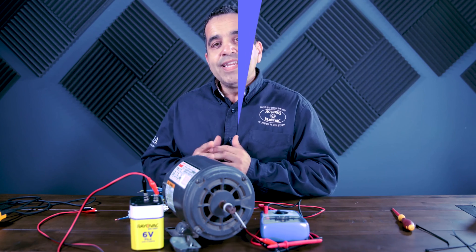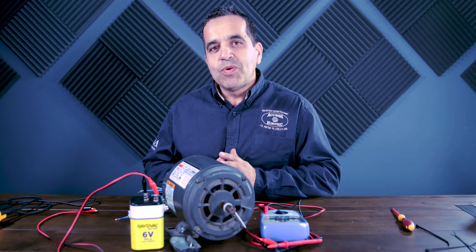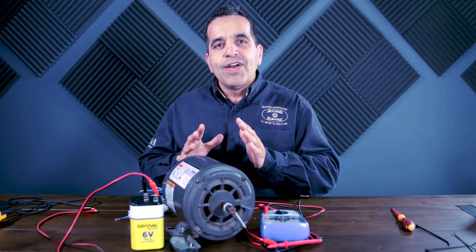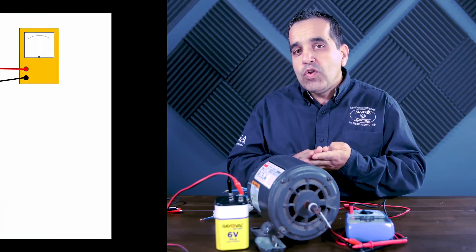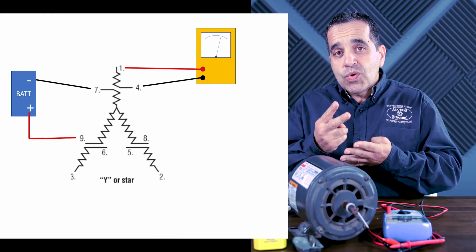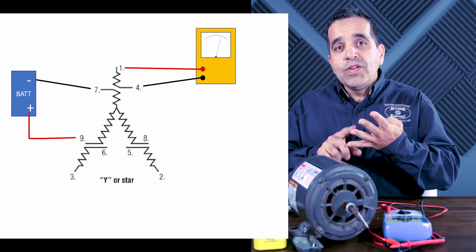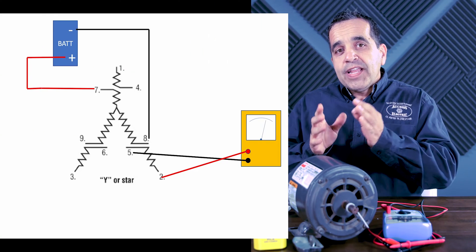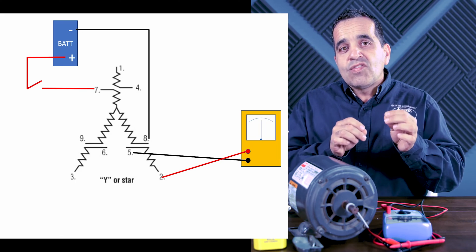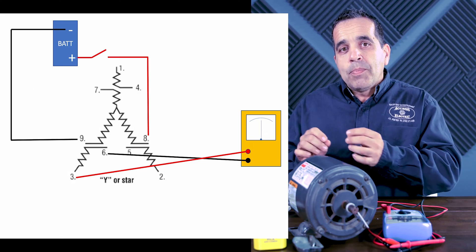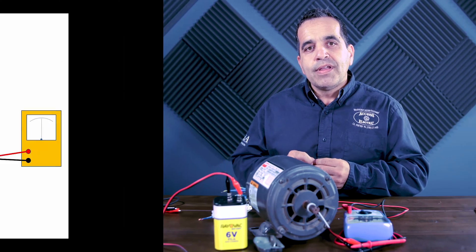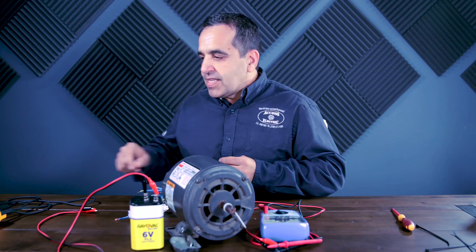So with a 9-lead Y-connected motor, you're going to have four groups of windings. You're going to have three groups of two and one group of three. And we're going to figure out which is which by using an ohmmeter to identify each group.